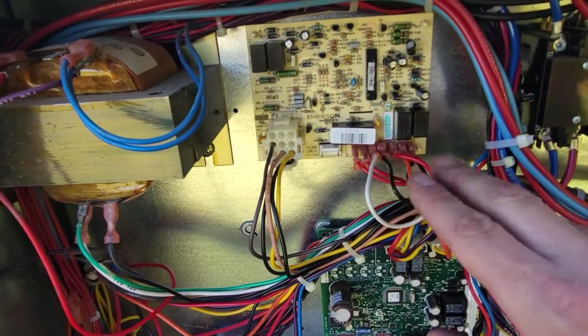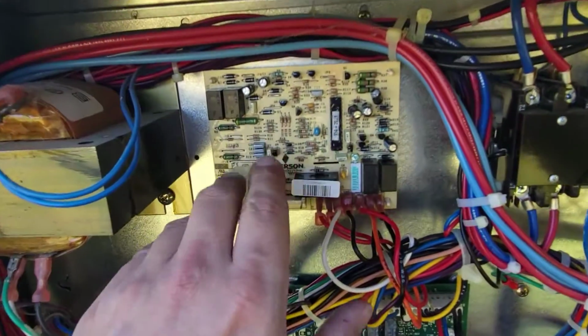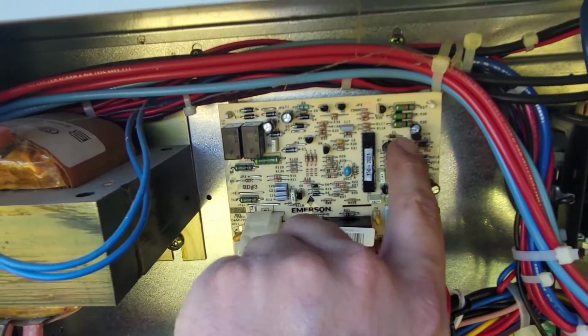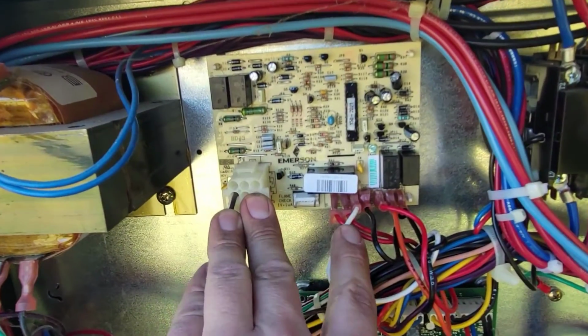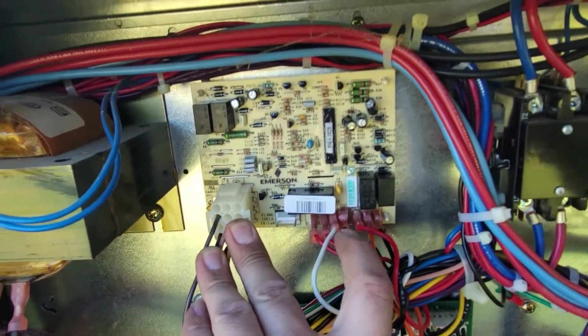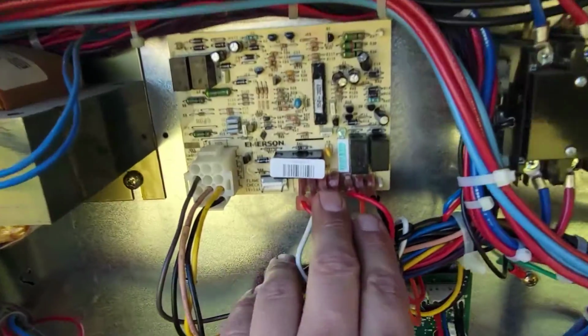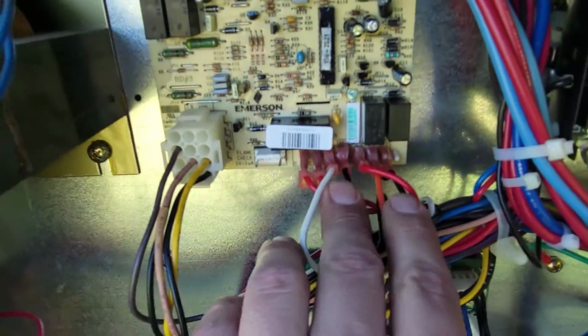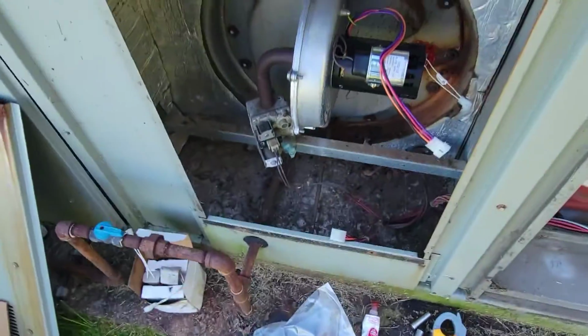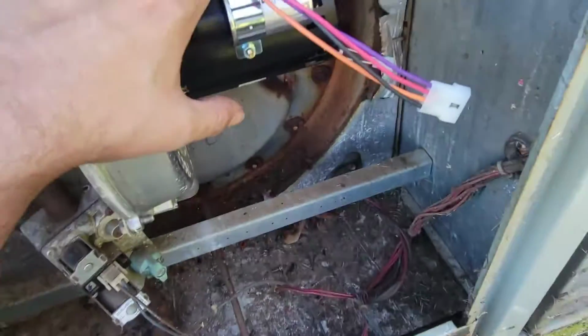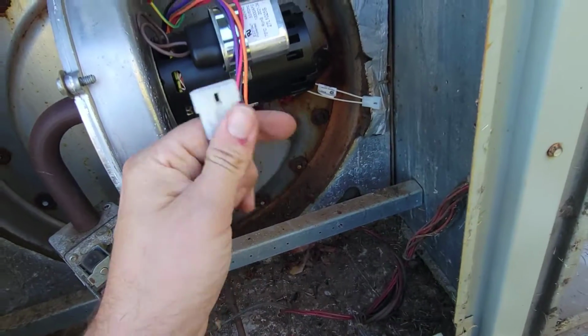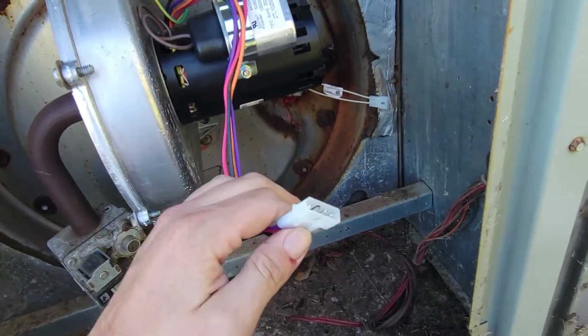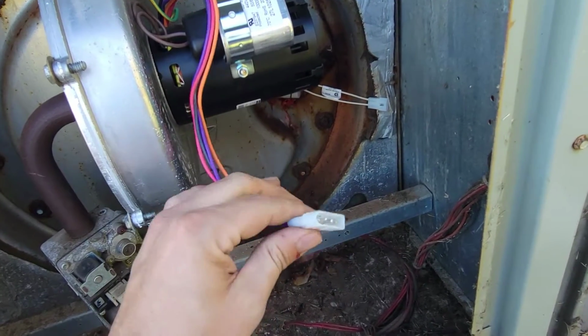This is a 9340. This is the ignition control board, and it was replaced because there were some burn marks up here. I went ahead and got a new board. But the problem I was having was this right here is what outputs voltage to that inducer motor, okay? And the inducer motor's right here, the new one. And I don't have it plugged up yet because I was reading ohms on the new one versus the old one. And that's how I figured out that I had a bad motor.